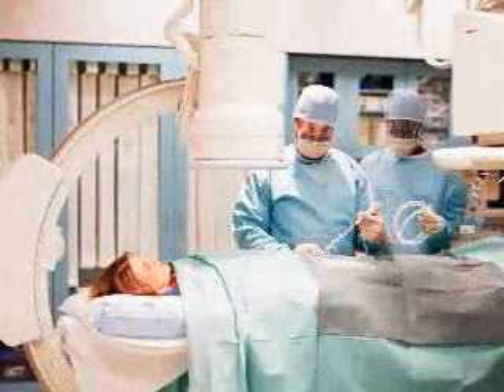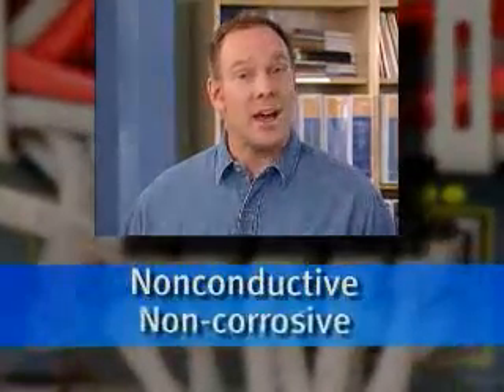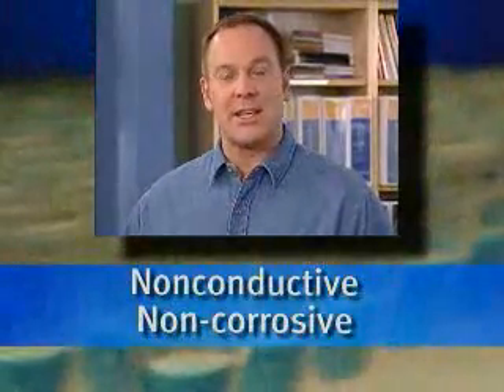First, they have a unique combination of properties that provide highly effective protection for facilities with high-value electronic equipment, such as telecommunications and data processing centers, healthcare, and high-tech manufacturing environments. They're electrically non-conductive and non-corrosive, so for example, healthcare facilities and financial institutions can remain operational 24/7. And because clean agents leave no residue, operations are back up and running in no time. But most importantly, clean agents are safe for use in areas where people are present, so employees have ample time to evacuate the area, something they might find extremely difficult to do in a room filled with smoke.